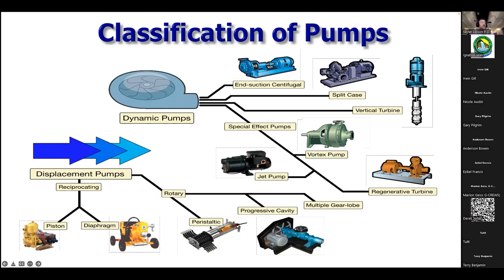Peristaltic pumps, also called hose or tube pumps, are used in auto samplers and are very common for chemical injection. Diaphragm pumps are also very common for chemical injection — brands like LMI are well known in this space. Piston pumps work like a large piston running in a cylinder, specializing in high solids content and commonly seen in solids handling. Small progressive cavity pumps can also be used for chemical injection, though less common.